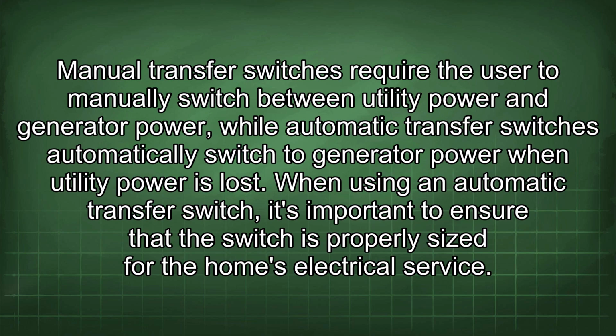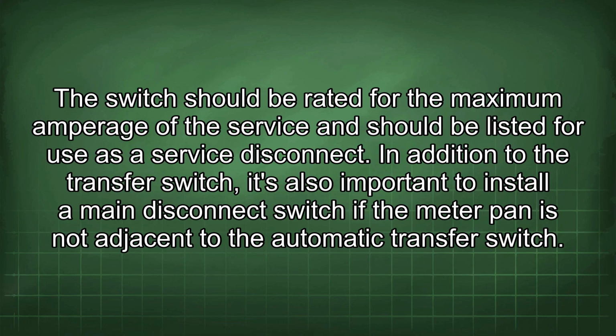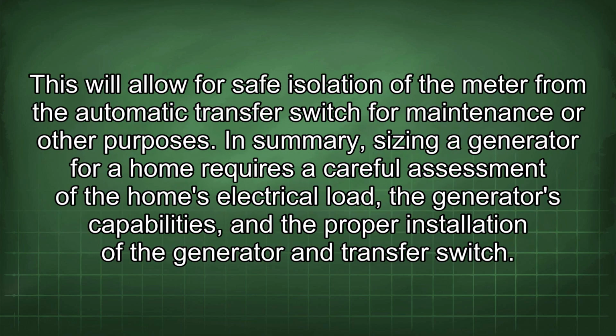When using an automatic transfer switch, it's important to ensure that the switch is properly sized for the home's electrical service. The switch should be rated for the maximum amperage of the service and should be listed for use as a service disconnect. In addition to the transfer switch, it's also important to install a main disconnect switch if the meter pan is not adjacent to the automatic transfer switch. This will allow for safe isolation of the meter from the automatic transfer switch for maintenance or other purposes.